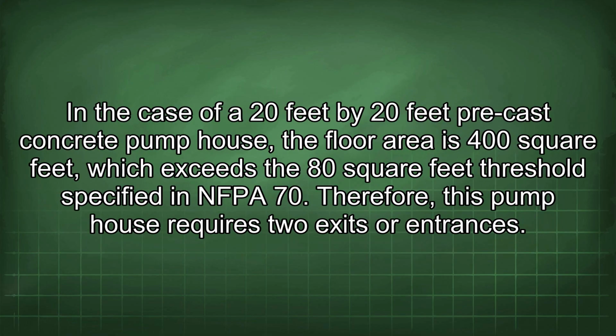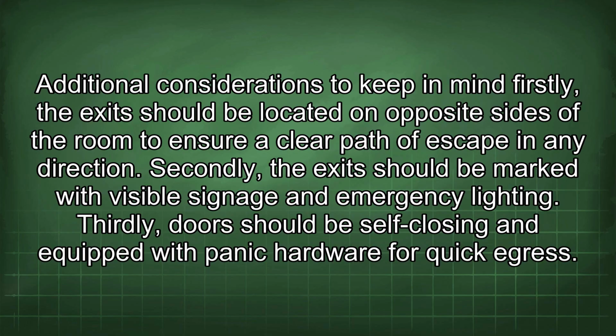In the case of a 20 feet by 20 feet precast concrete pump house, the floor area is 400 square feet, which exceeds the 80 square feet threshold specified in NFPA 70. Therefore, this pump house requires 2 exits or entrances. Additional considerations to keep in mind: firstly, the exit should be located on opposite sides of the room to ensure a clear path of escape in any direction.